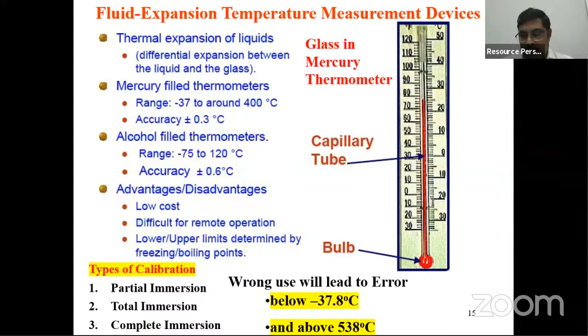Coming to this, this mercury glass thermometer is meant for measuring static temperature. That means it can give only the steady state temperature. Suppose the temperature is varying with respect to time, then it cannot measure. Basically, the time constant of these thermometers is very high. So the next version is the constant volume gas, or vapor pressure, thermometer, you can say. Basically, in the vapor pressure thermometer, there is a small bulb of very precisely measured volume. This bulb is connected to a pressure measuring device, which can be a simple manometer, or maybe a transducer, or maybe a Bourdon tube pressure gauge. When you keep this bulb in an unknown temperature medium, because of the heat transfer, the gas which is filled in the bulb will expand and create a pressure. This pressure can be measured either by using a simple manometer or maybe a pressure sensor. From the pressure, then you can measure the temperature. So here we need to have a very precise calibration between the pressure and the temperature.